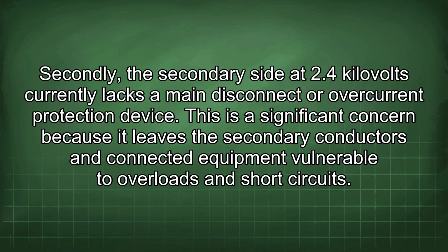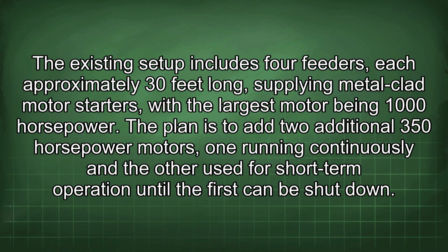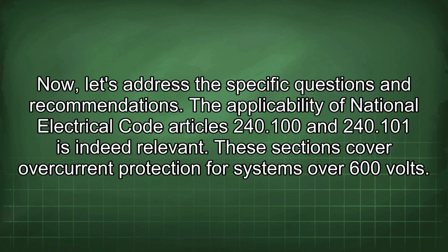Secondly, the secondary side at 2.4 kV currently lacks a main disconnect or overcurrent protection device. This is a significant concern because it leaves the secondary conductors and connected equipment vulnerable to overloads and short circuits. The existing setup includes 4 feeders, each approximately 30 feet long, supplying metal-clad motor starters, with the largest motor being 1000 horsepower. The plan is to add 2 additional 350 horsepower motors, one running continuously and the other used for short-term operation until the first can be shut down. Now, let's address the specific questions and recommendations.